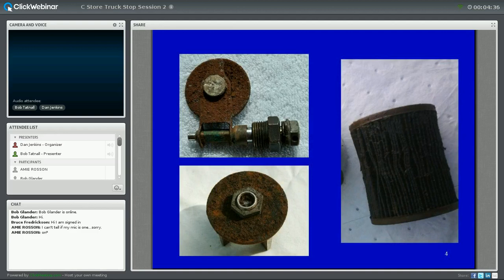The other thing we want to talk about today on the corrosion side, this is not just a downtime issue. This is a safety issue. So over on the left here, we have some valves. I met a gentleman in St. Petersburg, Florida. He does warranty claims on tanks, and he showed me a 5-gallon bucket full of these valves, and they're causing the dispensers to stay open or stay closed. And so fuel is leaking, particularly when something hits a dispenser or a dispenser goes bad. So we're going to talk a little bit about safety today.